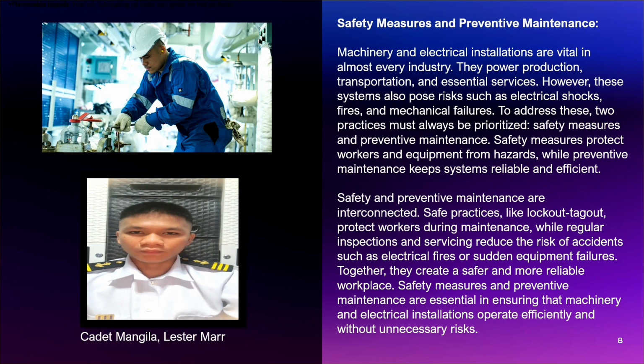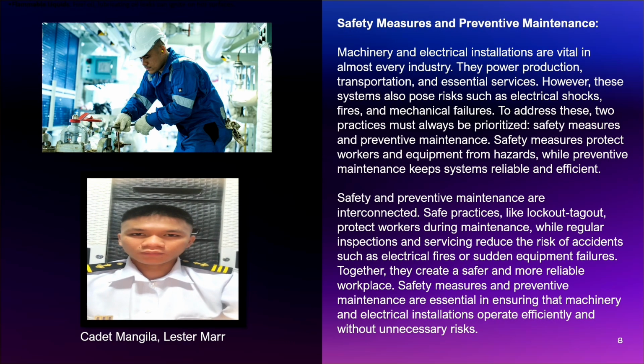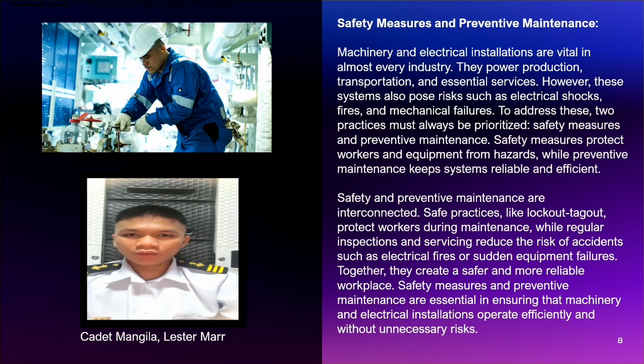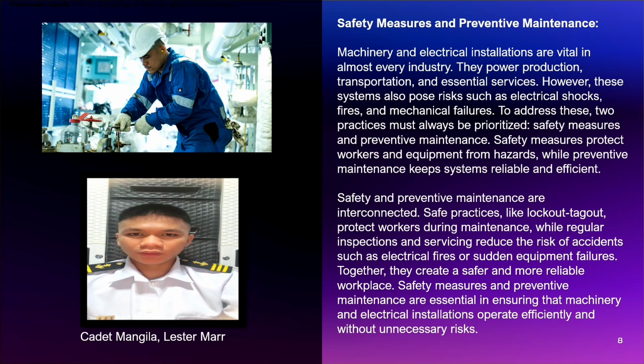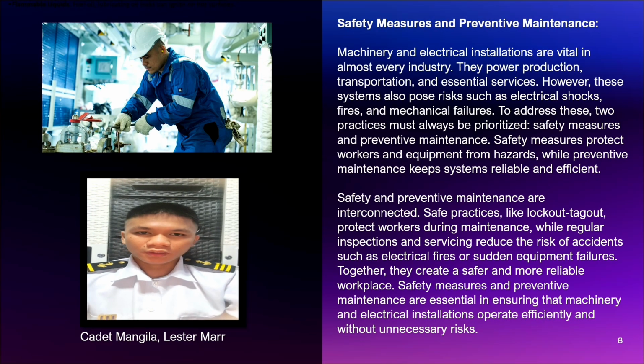Now, let's move to preventive maintenance, or PM. This is the planned, proactive approach to avoid sudden breakdowns and keep system efficiency. First, we have regular inspections. Machines and electrical systems must be inspected daily, weekly, or monthly, depending on their usage. Checking for loose wires, overheating, or unusual vibrations helps detect problems early. For example, spotting a small oil leak before it spreads can prevent catastrophic motor failure.